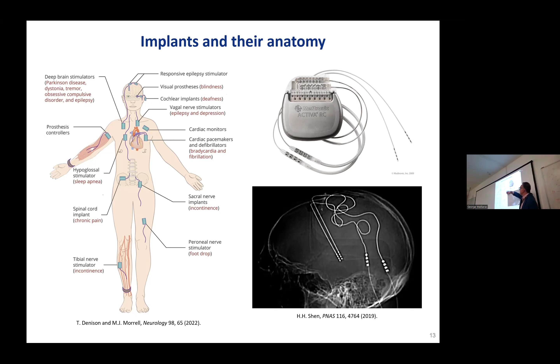The implantation of this is permanent. You don't want to move it. There are people with implantable electrodes for over 20 years today, and this doesn't move. This has to come out every couple of years to replace batteries, typically 5 to 10 years to replace batteries. And you disconnect from here, you take it out, put a new one in, connect it, and that's it.